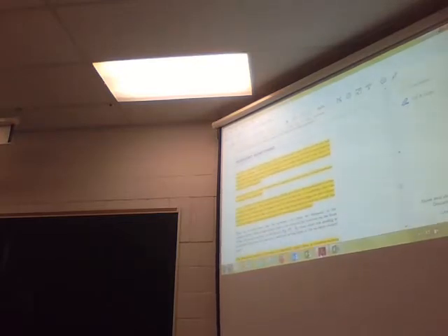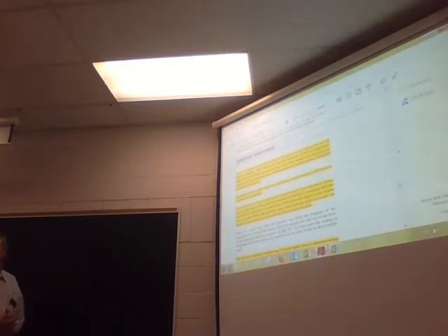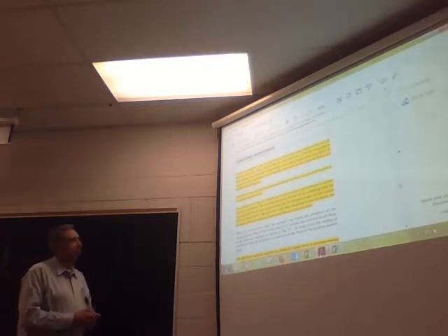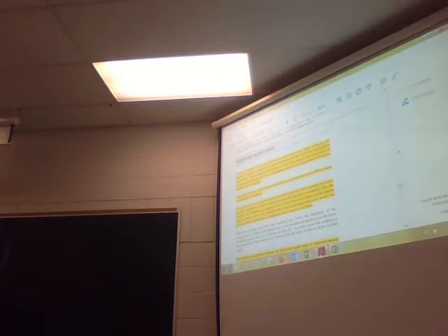Okay, dew point monitor. Dew point is defined as the temperature at which water vapor in the air will begin to condense. It changes with pressure and temperature. Remember, if the air temperature drops below the dew point temperature, at any time liquid can form. In a compressed air application, you will hear it referred to as atmospheric dew point or pressure dew point. Pressure dew point is the temperature at which moisture will condense at a system pressure. Different pressure, different temperature.